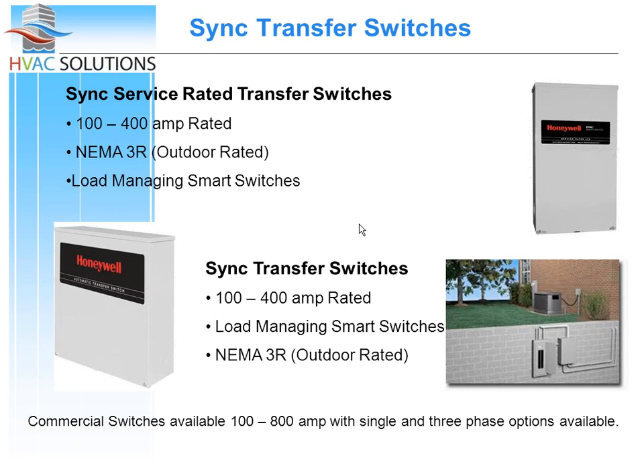The difference between a service-rated transfer switch and a non-service-rated switch is that a service-rated switch is going to have a circuit breaker inside of it. A non-service-rated switch does not. So all that really means is that it changes the positioning of the transfer switch in your system.